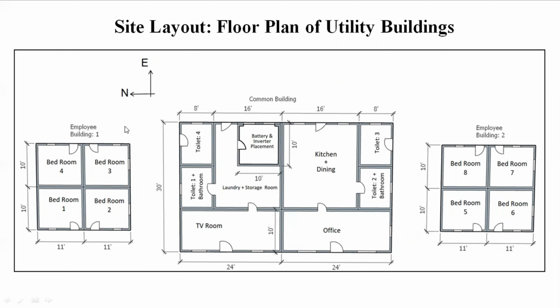Now there are 8 employees, so 8 bedrooms are designed in a manner that each employee gets a separate entry door and window. We have proposed to club 4 bedrooms as an employee building so that the conditioned wall area exposed to the ambient temperature is reduced, which will help in reduction of overall cooling load. As we can see, these 2 walls are now adiabatic, so rather than having 8 separate rooms, this setup will help in reduction of overall cooling requirement.